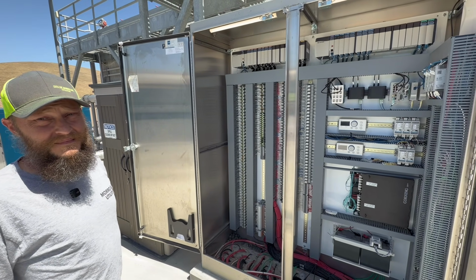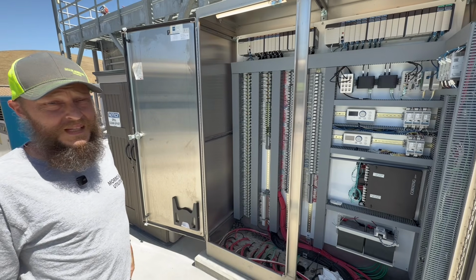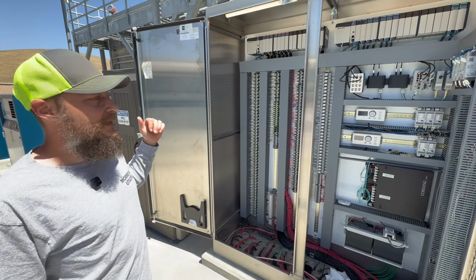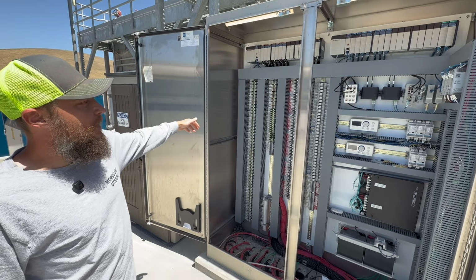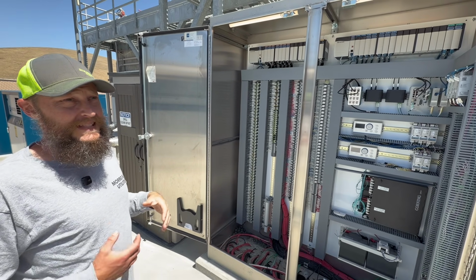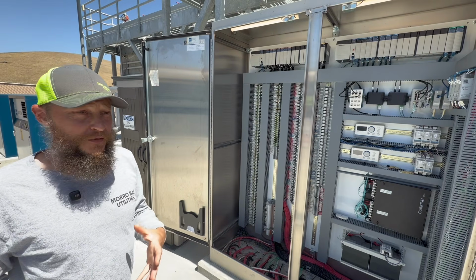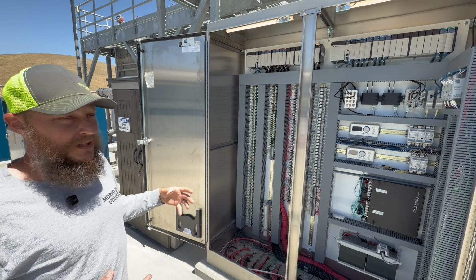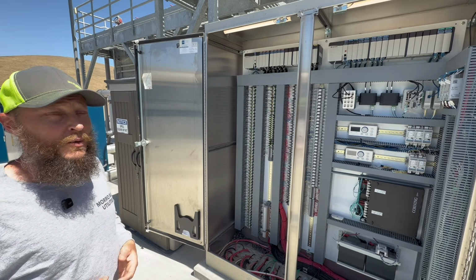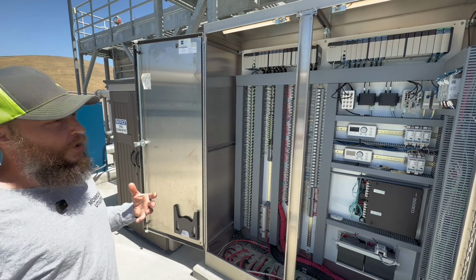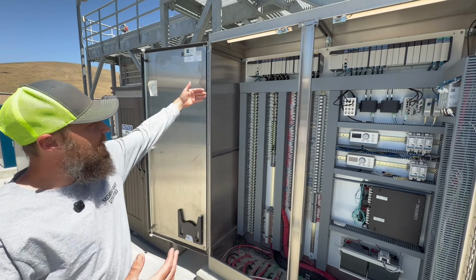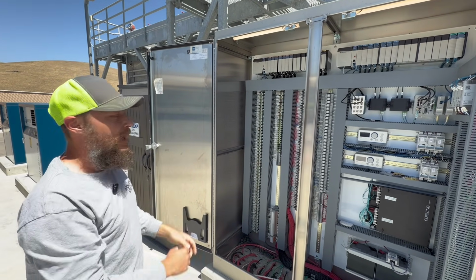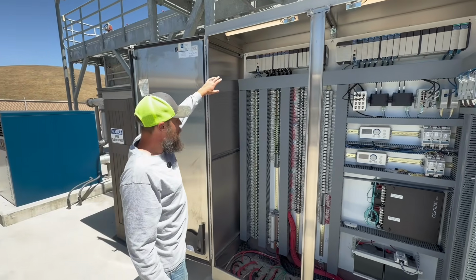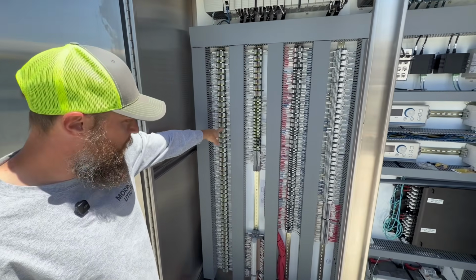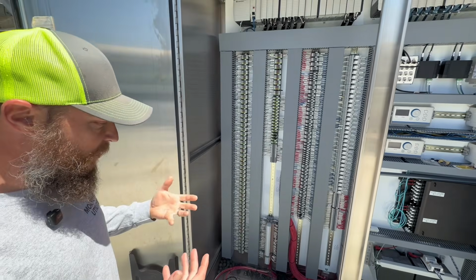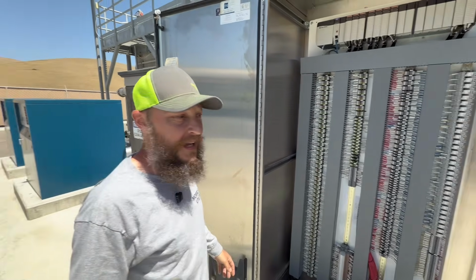Very cool. So we have seen the HMIs, we have seen the PLCs, we have seen the Historian, but what information is coming into the PLC? Like, what's the next step? Yeah. Working backwards, if we're going back out to the facility, the next thing we would go out to is a sensor. That's the actual source of the data, the source of truth for that particular number. So we're going to go chase down a DO probe that we looked at on the SCADA system and on the Historian. That DO probe is going to be outputting a signal, and we're going to take that as an input to the PLC. And that DO probe is going to be coming in over here on the analog input side. There are drawings that we can pull up and find it, but we're going to go out there on the deck and track it down.